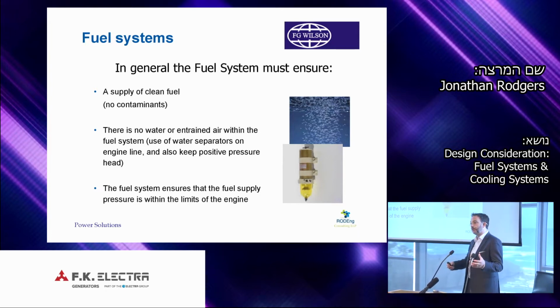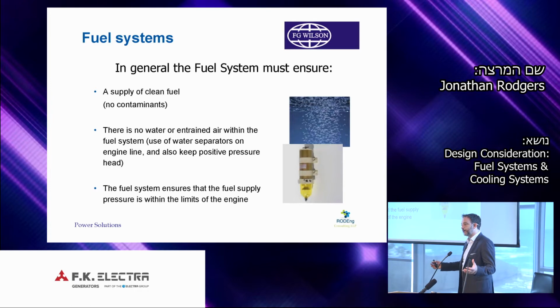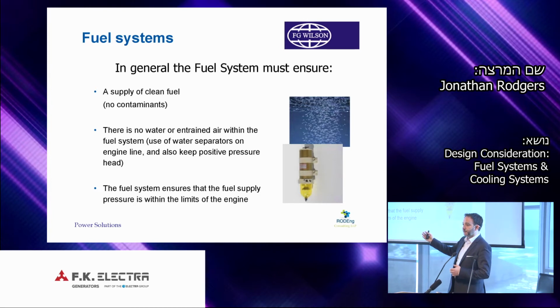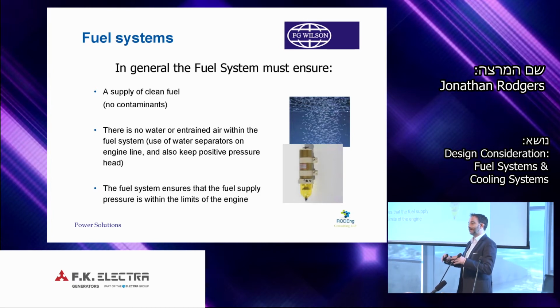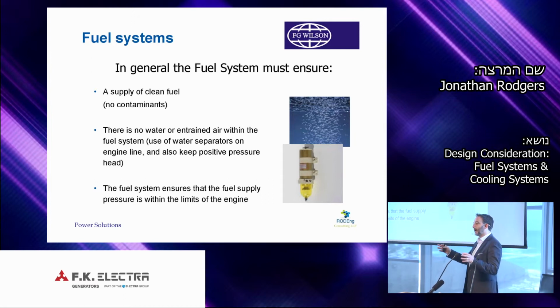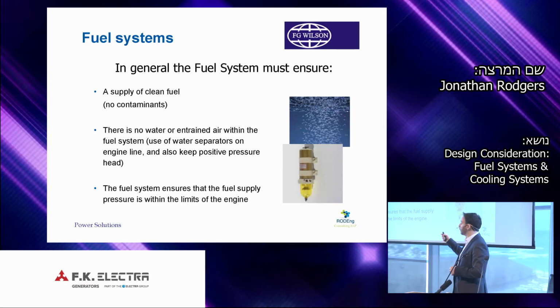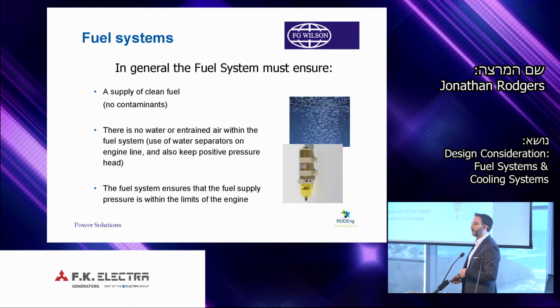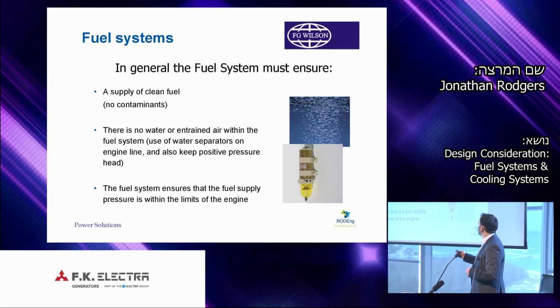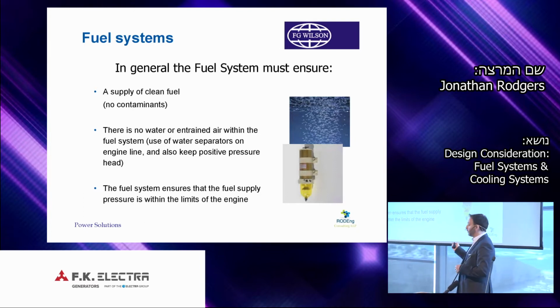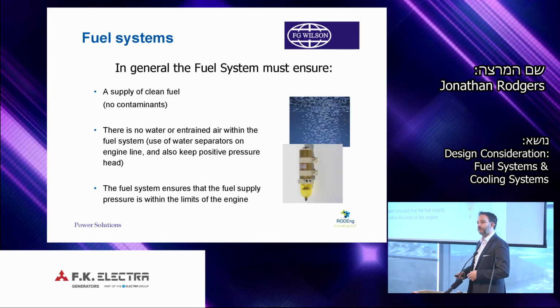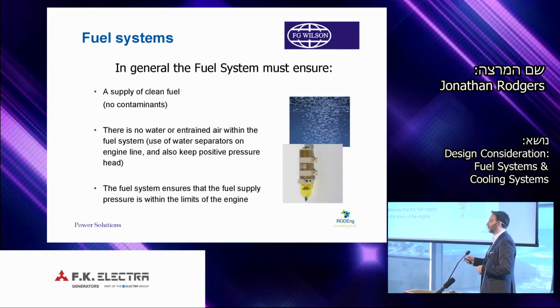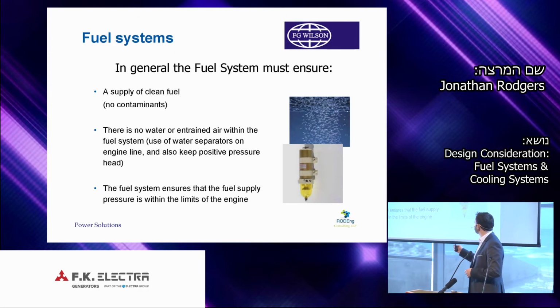We can have water with diesel fuel tanks, and we have metal fuel tanks. The difference in temperature from outside air to inside the tank would be approximately 8 degrees, and you will have condensation can gather within a tank. So that can bring water into your fuel system, which would interrupt combustion. So what we do is we look at how we filter and how we arrange water separation and how we design the system to avoid that water interrupting the engine performance.